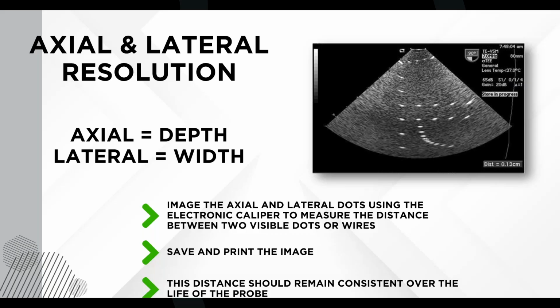The reason I picked the two smallest ones is because anytime I go back to redo this test, those are the smallest ones that I always choose from, the ones that I can see with the smallest distance. You can see the length here is 0.24 centimeters. If you saw any change or degradation in this the next time you did this test, it would indicate there could be an issue with the transducer. I've never seen this test be off, but it's one of the tests they asked us to do, so we go through and do it.